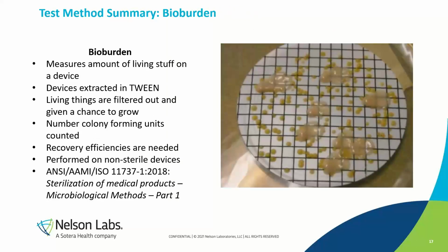Then moving forward to the biological side, bioburden, we're going to measure the amount of viable organisms on a device, extracted in tween, filtered, incubated, and then the colony forming units, the CFUs, are counted and reported. Like the other test methods, gravimetric, TOC, THC, recovery efficiencies are also required here. But unlike spiking with a chemical, the lab would be inoculating, or you could provide a device that's expected to have a high bioburden count on it, natural bioburden.